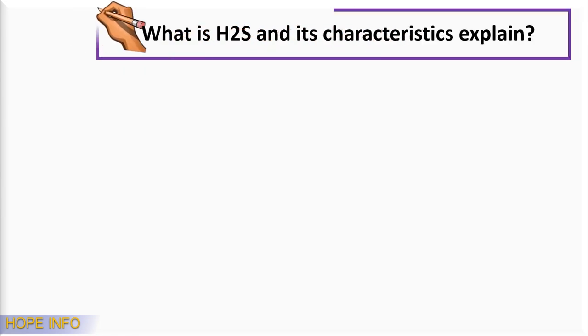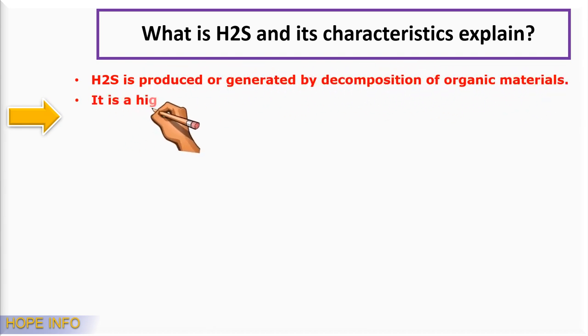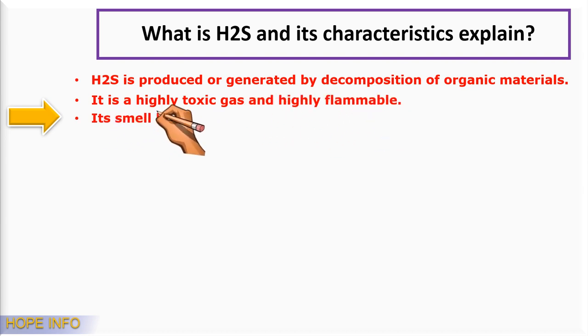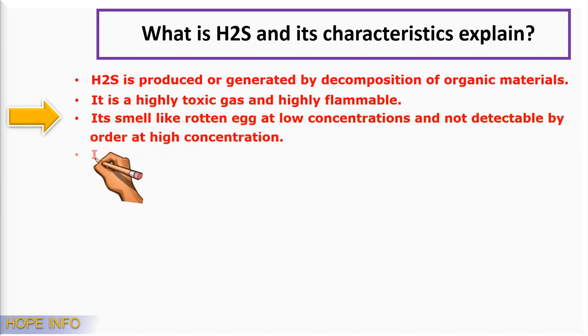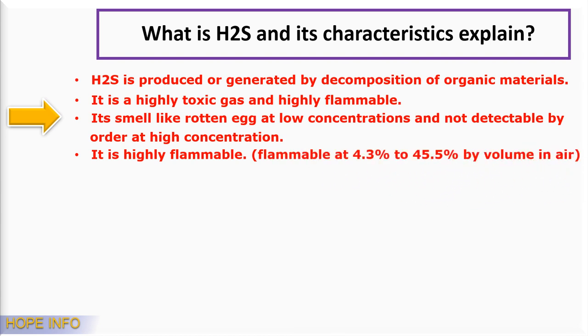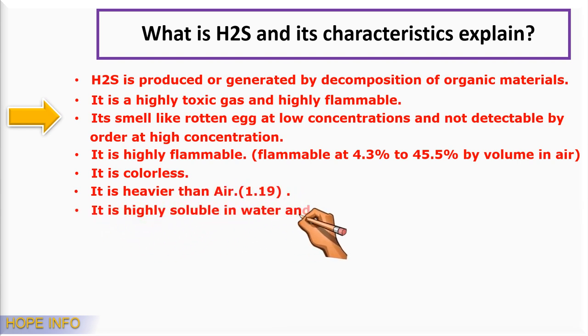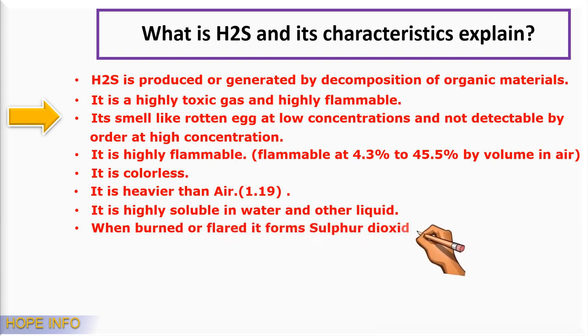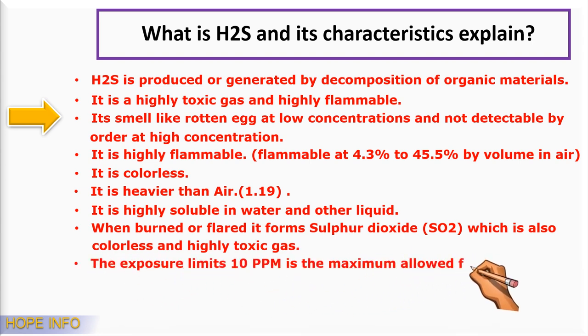What is H2S and its characteristics? H2S is produced or generated by decomposition of organic material. It is a highly toxic and highly flammable gas. It smells like rotten eggs at low concentrations and is not detectable by odor at high concentrations. It is flammable at 4.3% to 45.5% by volume in air. It is colorless and heavier than air (specific gravity 1.19). It is highly soluble in water and other liquids. When burned or flared, it forms sulfur dioxide (SO2), which is also colorless and highly toxic. The exposure limit is 10 ppm maximum, allowed for an 8-hour workshift.